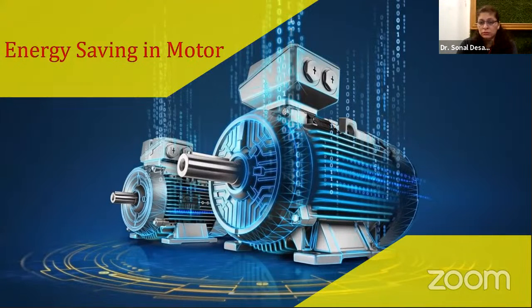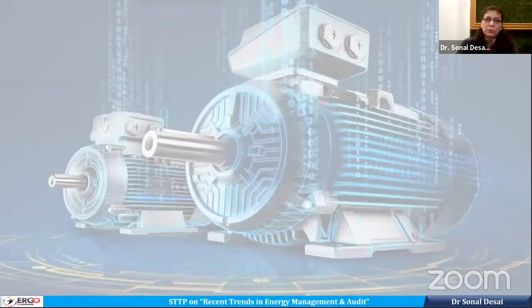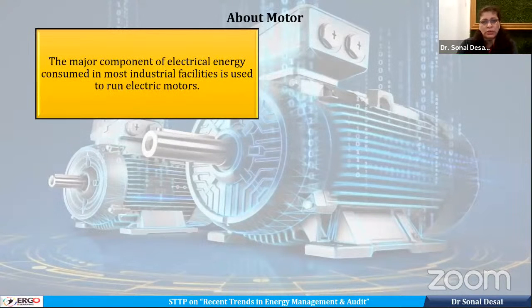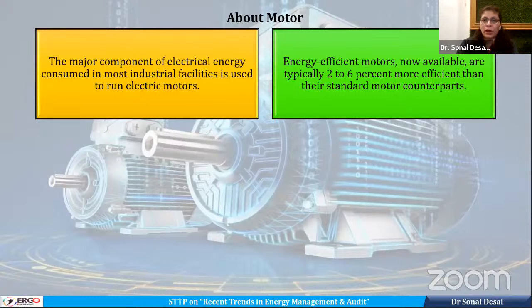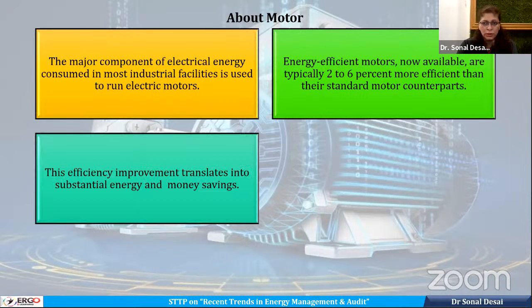Manufacturers are using words like super efficient, energy efficient, hyper high efficient. So those are also misleading. And hence there are multiple myths when we talk about energy efficiency of motor. And one needs to consider these facts before deciding the type of motor to be used. As I just said, the major component of electrical energy in industry is consumed by the electrical motor. Energy efficient motors which are available now are 2 to 6% more efficient compared to standard motors which are used in practice. Efficiency improvement translates into substantial energy and money saving.